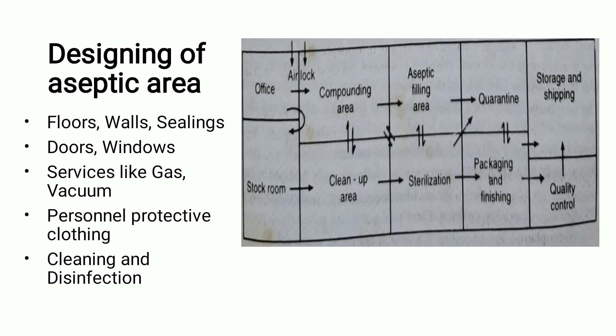Looking at the layout diagram for an aseptic area, there is only one-directional movement throughout. A person entering from the office through an airlock door can only move toward the compounding area or the stock room. From the stock room, movement goes to the cleanup area, sterilization, or packaging. From the compounding area, the flow goes to aseptic filling and then quarantine. Movement in reverse — for example, from sterilization back to cleanup, or from packaging back to sterilization — is not permitted.